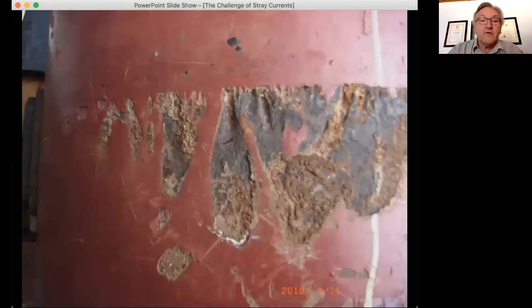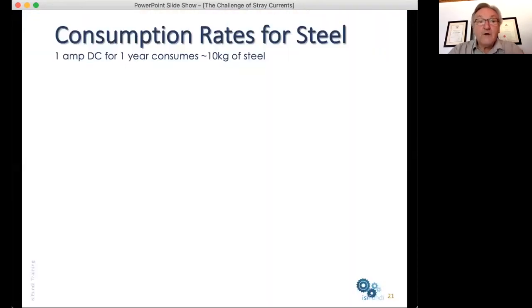This is a photograph taken of a pipeline which was buried, obviously, and it was coupled, not continuity bonded. And the line that you can see here was the edge of the coupling. And this corrosion has taken place because of stray currents that were in the soil, got picked up by the pipe, and then discharged back to soil on its way back to its original source, i.e. the traction substation.